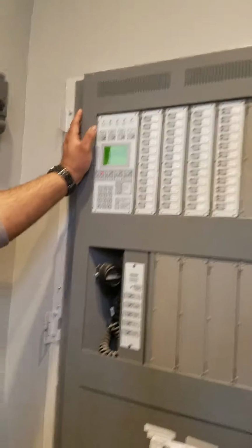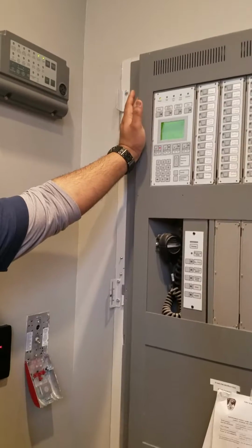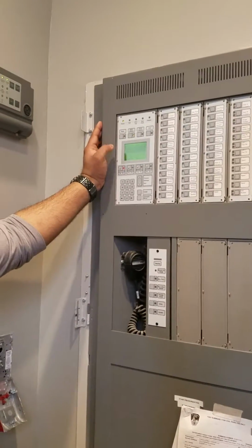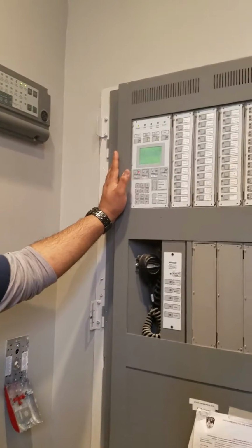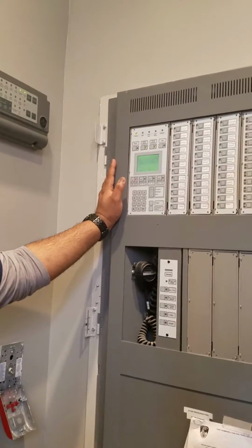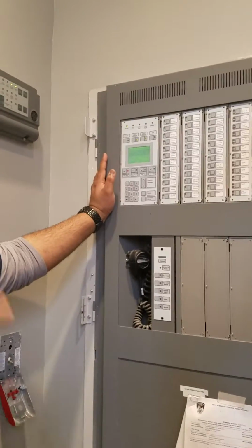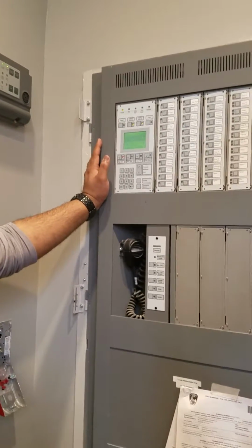Let's say we are offline with Central Station, and an alarm comes in, the panel's on, it's not on test, but we're offline. We'll silence. And let's say for whatever reason you try to reset this point and it's not resetting. Sometimes it happens with smoke detectors, especially if there's too much dust in the air. You would try to reset it, it would probably clear for a minute or two, and it would go back into alarm.